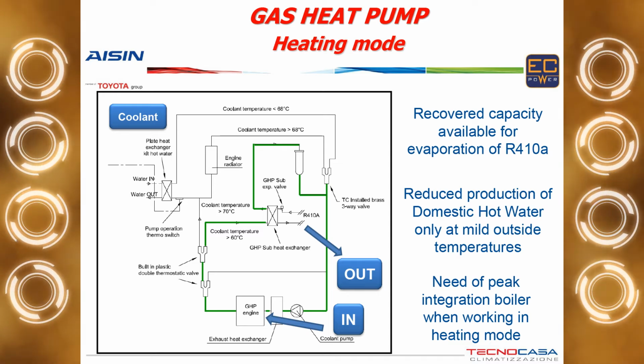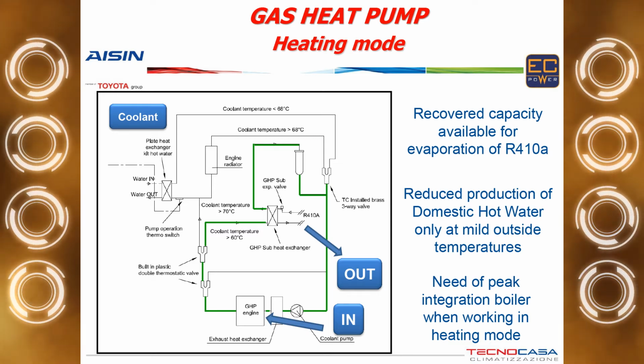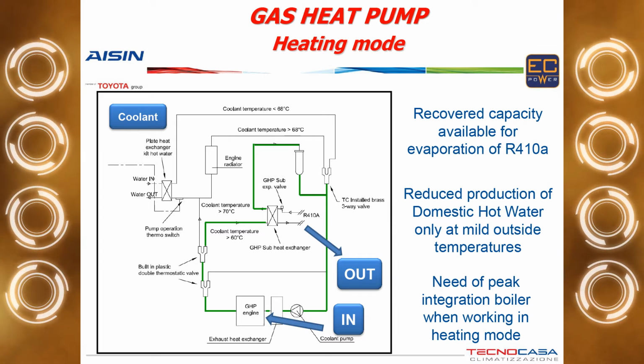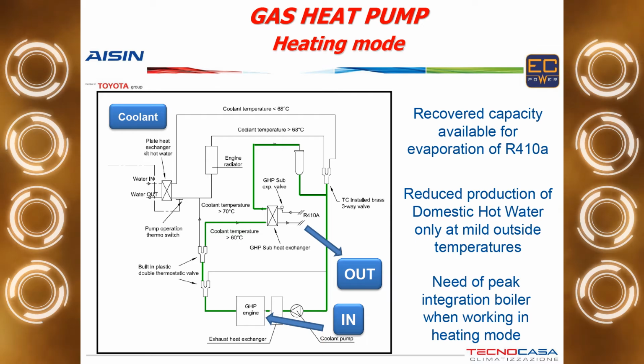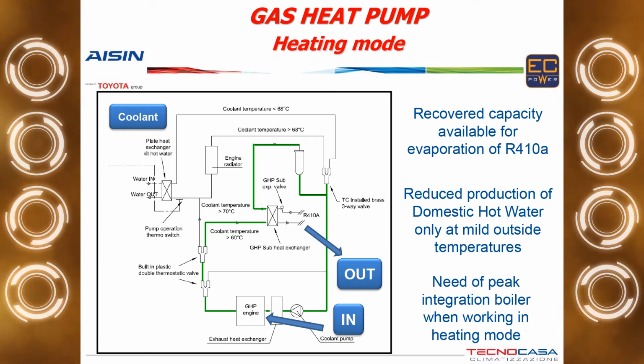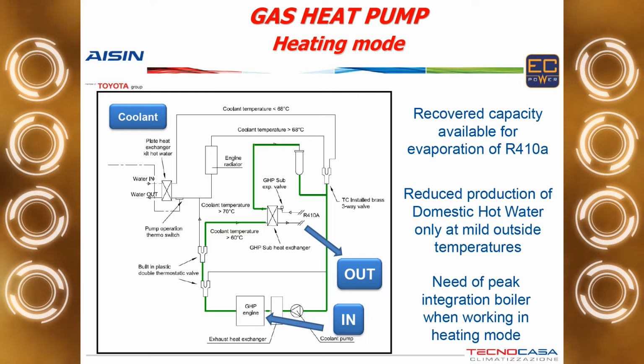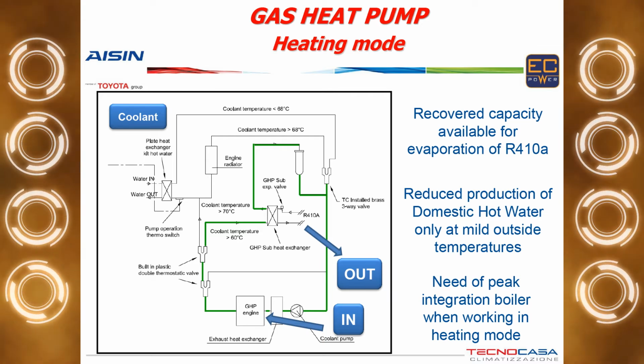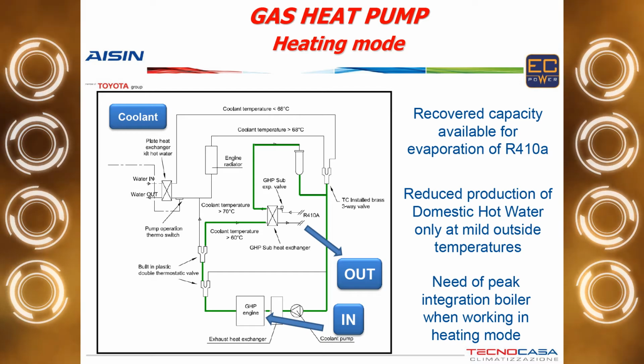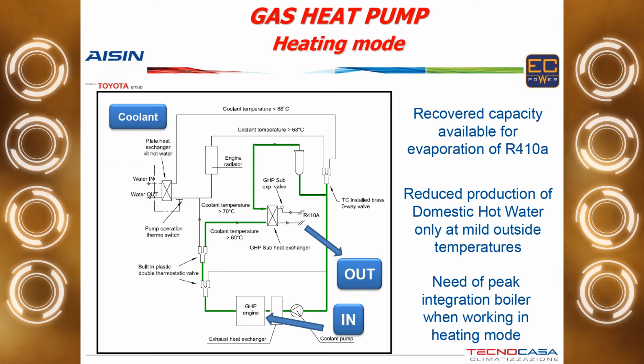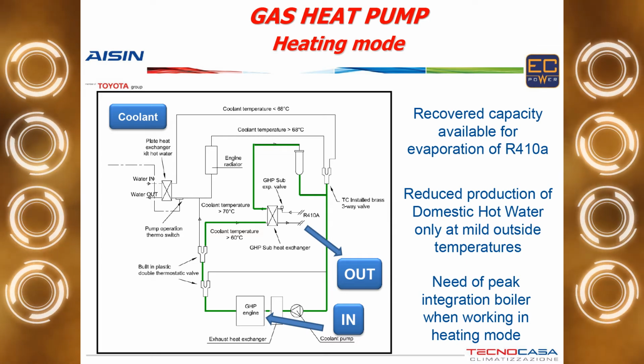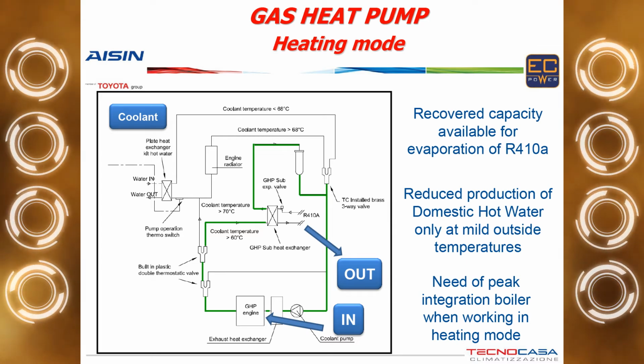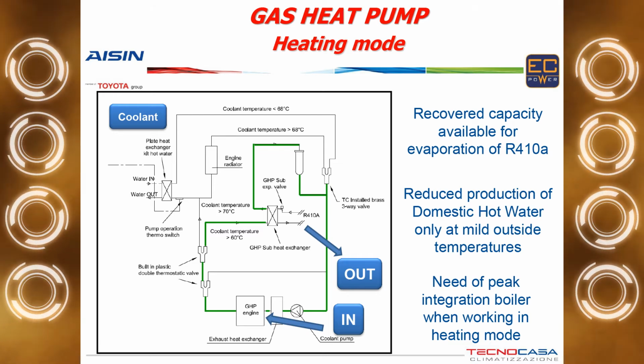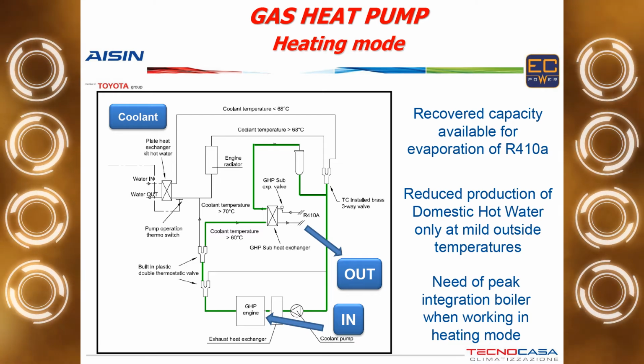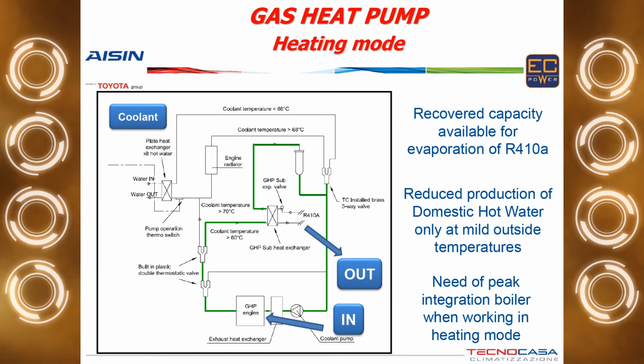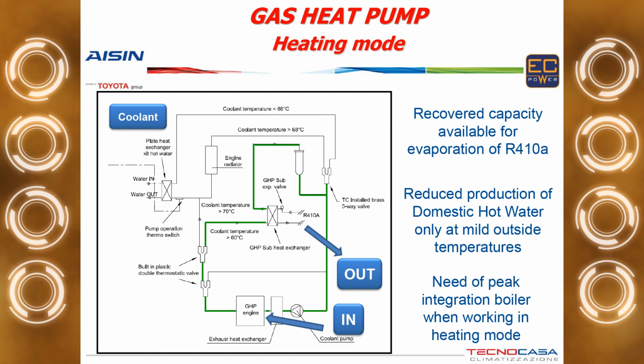So in this case, the recovered heat from the engine and from the exhaust gas is used for the evaporation of the mixture. In fact, when this is happening, we don't have enough temperature to open the thermostatic valve to the domestic hot water kit. So most probably during the winter, there won't be any recovery, or a very small quota can be recovered. So we have to think of something else to produce the domestic hot water when the unit is not working or when the unit is working in heating mode. There is, as I told you, a need of peak integration boiler, but it can also be something else. I mean, if we have a cascade heat coming from somewhere else, we can take advantage of this cascade heat.